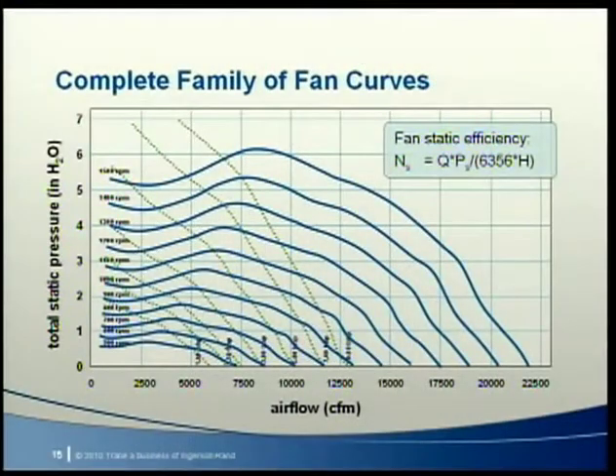Repeating these calculations for each test point results in a complete fan curve at a new speed. New curves for brake horsepower can be developed similarly. Here's an example of actual fan curves for a specific fan in an air handling unit showing performance at different speeds. The brake horsepower curves show how much power the fan needs at each operating point, and fan static efficiency lines can also be included — though usually not published — and can always be calculated using the efficiency equation.